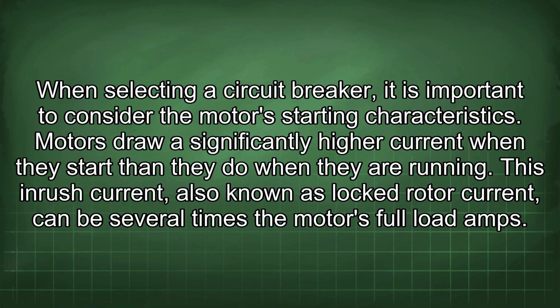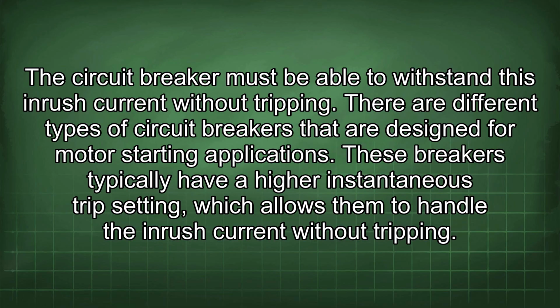This inrush current, also known as locked rotor current, can be several times the motor's full load amps. The circuit breaker must be able to withstand this inrush current without tripping. There are different types of circuit breakers that are designed for motor starting applications. These breakers typically have a higher instantaneous trip setting, which allows them to handle the inrush current without tripping.